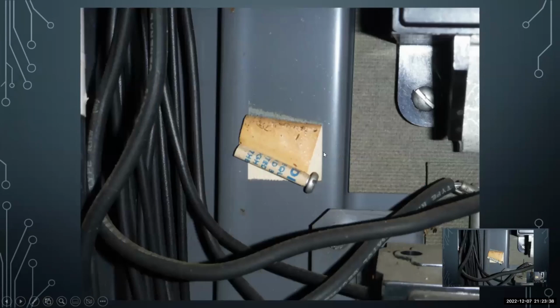Yes. My quick question. Okay. Why can you double up ground wires in a bus bar, but not neutrals? Probably the main reason for that is, like we talked about earlier, they're not carrying current unless there's a fault. So they're not getting heated up, cooled off, heated up, cooled off like a neutral is. Neutrals are being energized, de-energized, so a neutral needs a good, secure, single termination, where the equipment grounds don't. And I wouldn't be surprised to see it become more stringent in the future, where they may not allow doubling up the equipment grounds. I don't know, but that's why it's not under load in a normal situation like a neutral is.